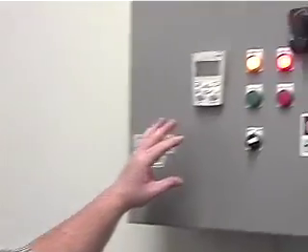One thing we should point out as well, and we can confirm with the BAS guy, is that we have end switches on the relief fan dampers. What we're doing with that is we don't want somebody to come into the VFD in hand or just override the VFD on with the dampers shut and blow off. So we are tied to the safety circuit of these VFDs on the 5 relief fans: if the damper's not open, it goes to the safety and shuts down the VFD so it won't run.